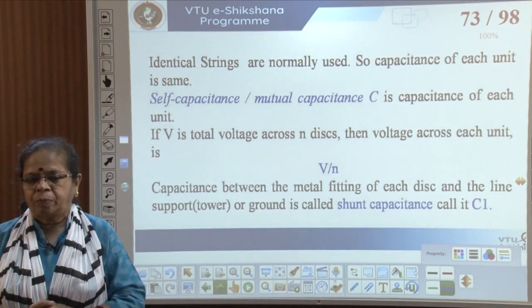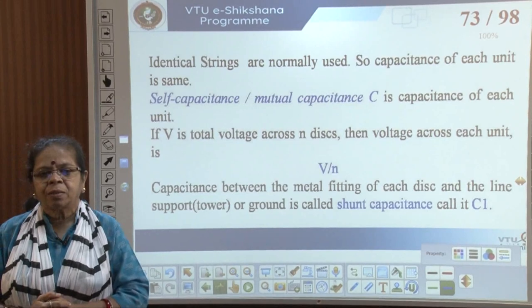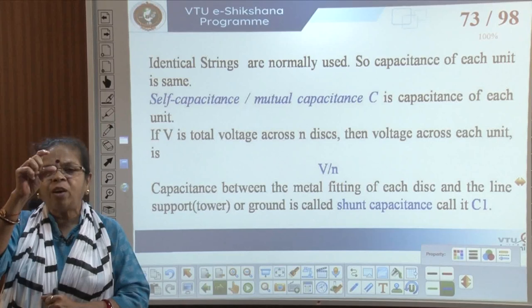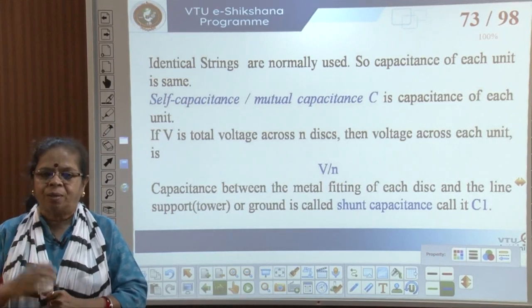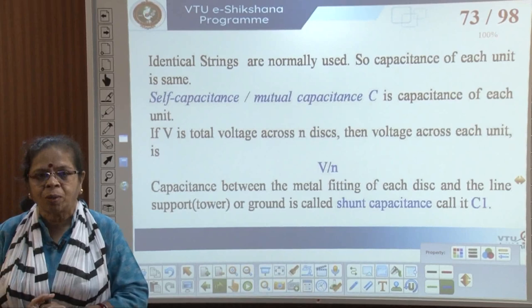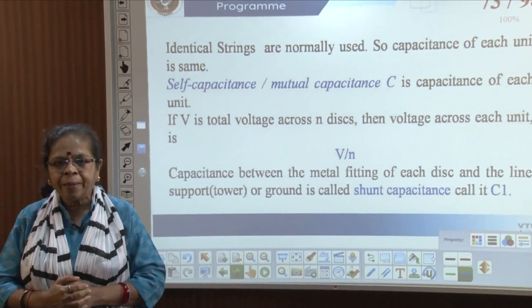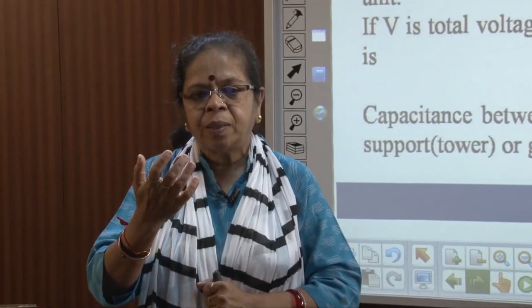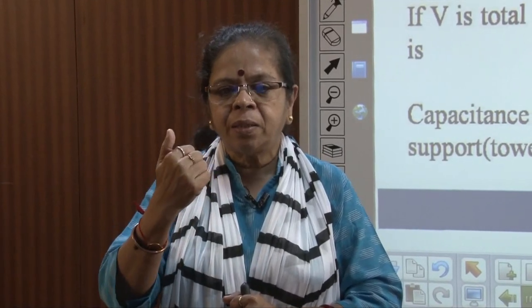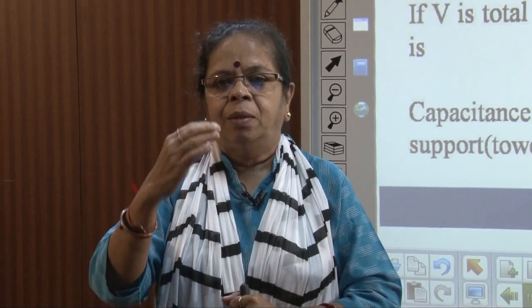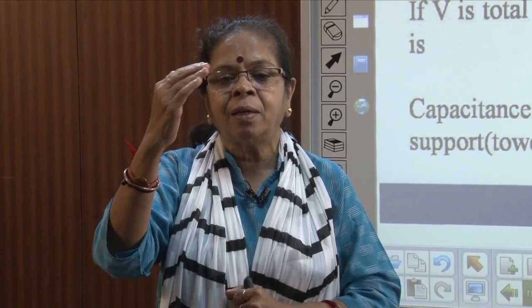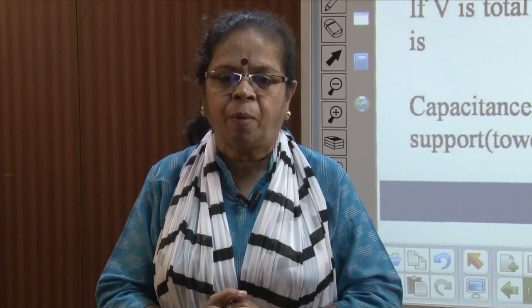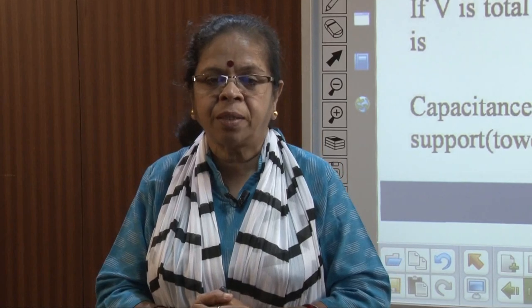However, this is not the full story. There is also capacitance between the fitting of each disc and the ground or the supporting structure — which could be a tower. This is called the shunt capacitance, denoted by C1, and it disrupts the expected equal voltage distribution.